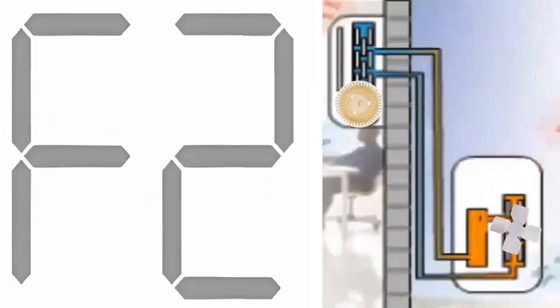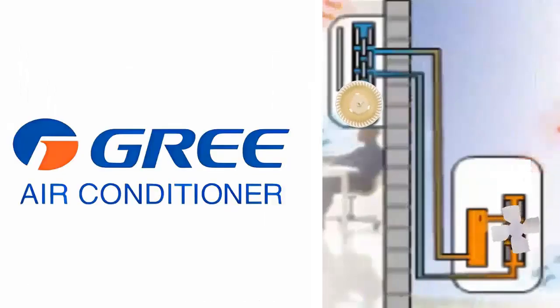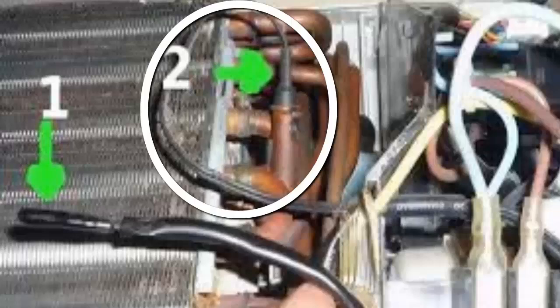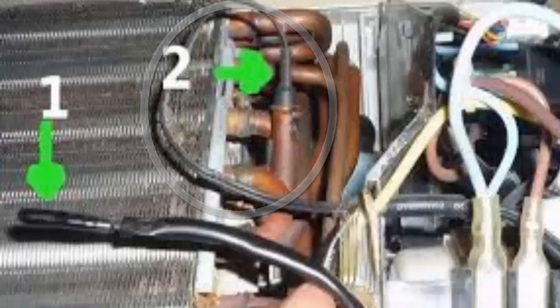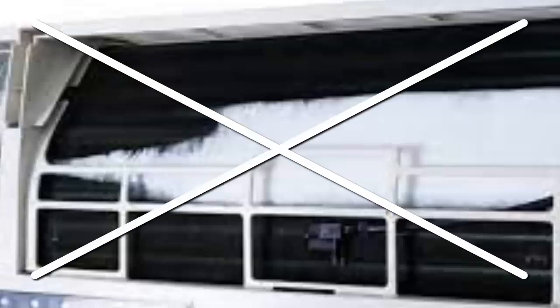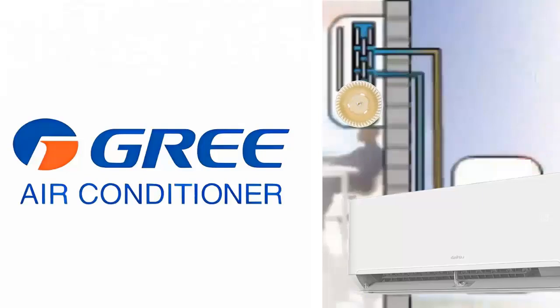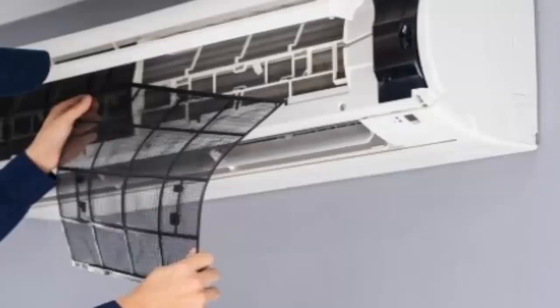Code F2 indicates an issue with the indoor coil temperature sensor, which measures the temperature of the refrigerant gas in this area to prevent coil freezing. In case of freezing in the indoor unit, it is recommended to check the proper operation of the indoor unit's fan and clean the air filters to ensure good airflow in this area and optimize heat exchange.